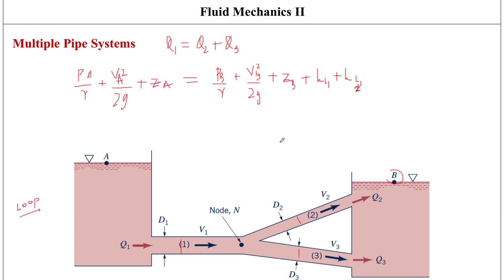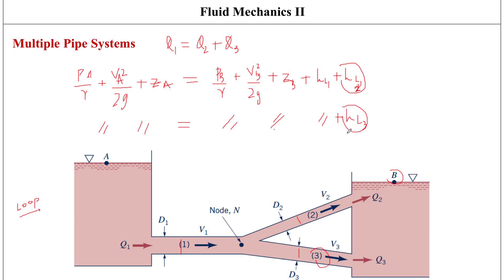Writing the same equation for the third pipe gives an identical form, so we end up with: pressure at A plus velocity plus elevation plus head loss of pipe one plus head loss of pipe three. This means the head loss for pipe two must equal the head loss for pipe three. Although the pipe sizes and flow rates can be different, this is the condition the loop system must fulfill. Combining the two equations gives: head loss at pipe two equals head loss at pipe three — the major governing equation for the loop system.